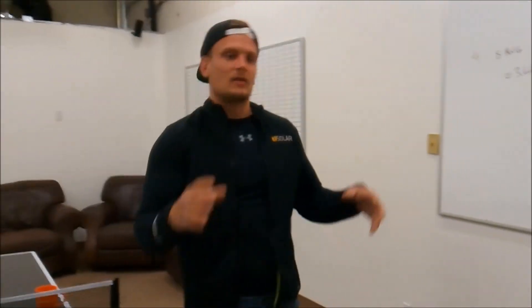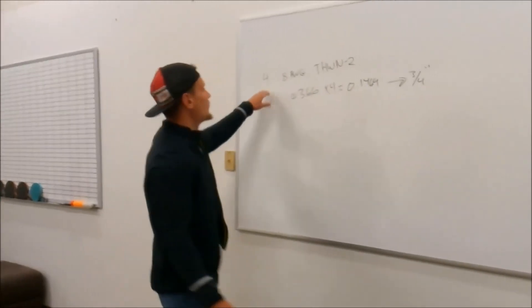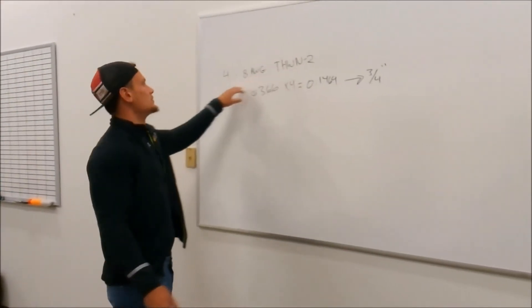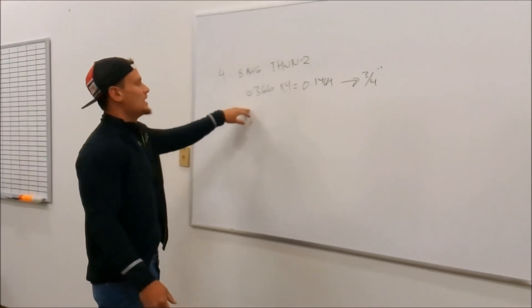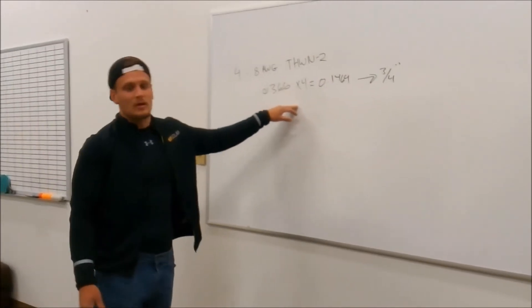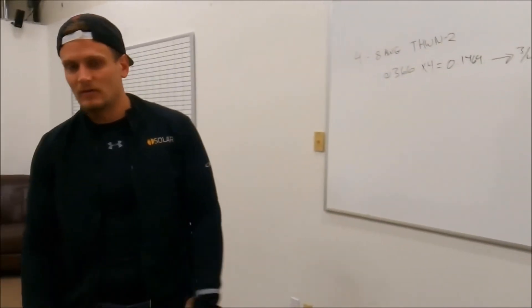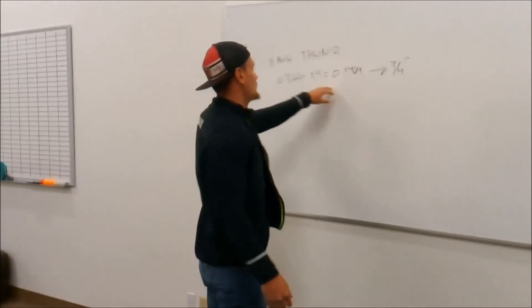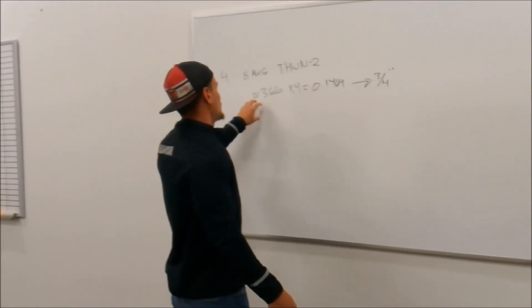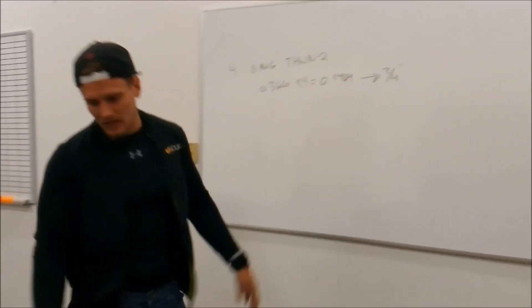So the reason that you would need these other tables is if, say we had 4, 8 gauge THWN2s, but then we had another 2, 8 gauge RHW wires. So then we have 2 different areas that we have to solve for. Even though it's the same gauge, they have a little bit of a different area. So we take this number, and then we'd say, the 8 gauge RHW wire is, we'll see where that is.